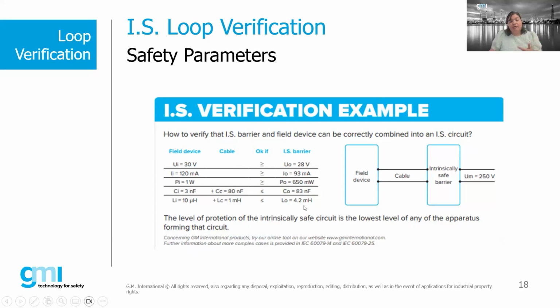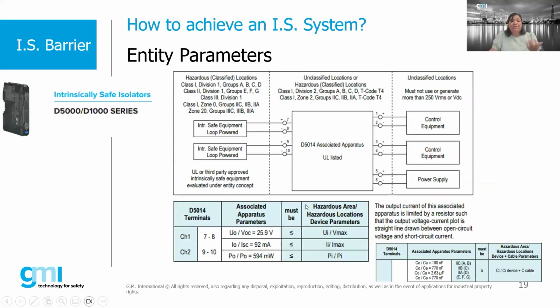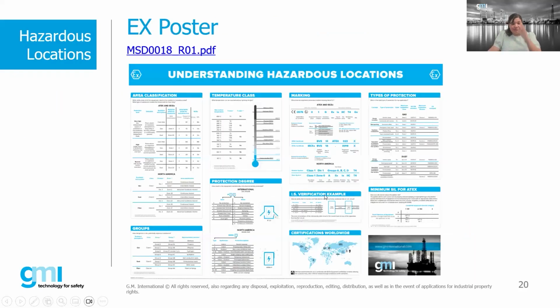We have it as part of our poster, which I'm going to show you later on. It's an example of an IS barrier, happens to be a galvanic isolator barrier, where it tells you this is the associated apparatus and these are the values of the associated apparatus. Then you need to put in the values of your device and follow the rule. On the same document, you'll have the information for the cable, and it will tell you what to do. So you're just looking for this information and filling in the blanks, pretty much. That's what you need to save as your documentation for inspections.